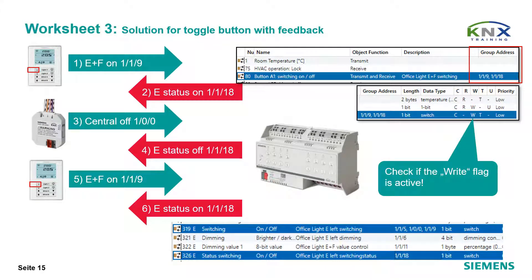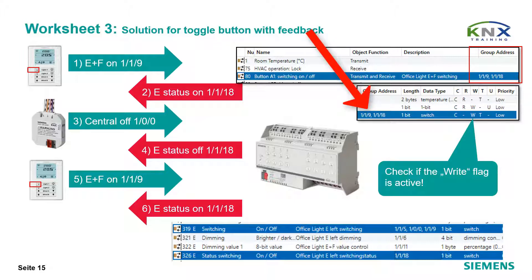Solution for toggle button with feedback. A toggle button will always send the inverted status of its output object for switching. But if you link this object just to one group address, the button will not receive changes from the actuator if that actuator is controlled by further group addresses. The result is: if you turn the light on by the toggle button but off by the push button interface for central off, the next operation of the toggle button would also send off and nothing would happen, as the light is already off. The solution is to link the switching object of the push button also to a status address of the controlled actuator channel. Make sure that in this case the status telegram finds an active write flag in this object, so that the object value can be overwritten or simply updated.